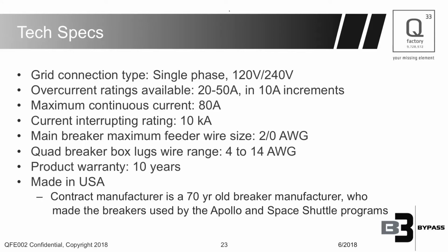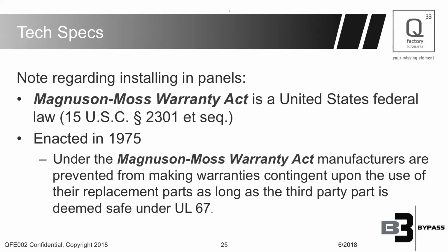And then one comment I want to make here is we are made in the USA. We have a contract manufacturer that's located in Chicago. This contract manufacturer is over 70 years old. They made breakers for the Apollo space program and all the breakers for the space shuttle program. So we didn't want to cut any corners, and safety is first and foremost to us. So this manufacturer is very near UL. They do all of our UL testing with us and for us, and have a lot of experience in making industrial quality breakers.